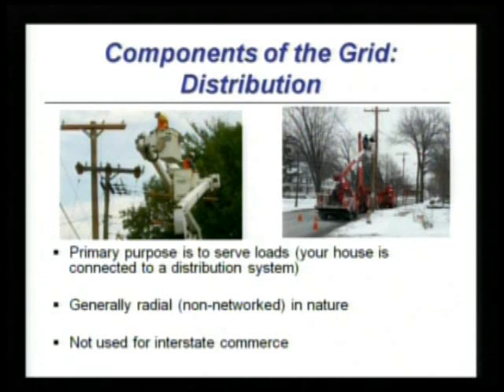The distribution portion of the grid typically is radial in nature, which means a line runs out and has no other interconnections to it. So if you lose that line, all the load along it is lost. There's fundamentally no way to backfeed or loop that system in. So it's typically the type of thing you see when wooden poles run down your neighborhood road, relatively short, with relatively small insulators on them. This is a typical distribution line.